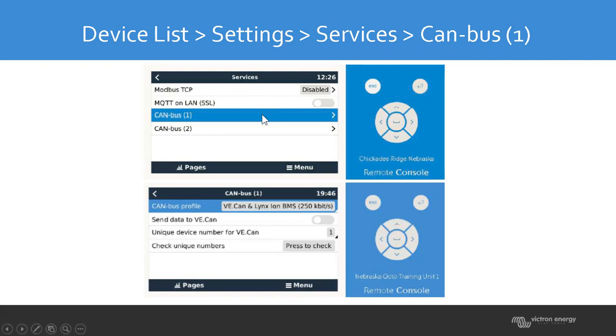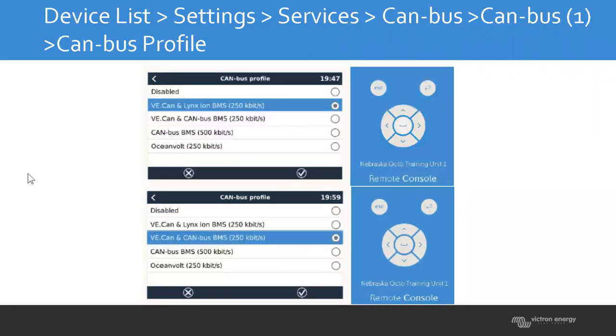This is a shot you'll see of the CAN bus. We get into that CAN bus, and it'll say CAN bus 1. Once you get into that, the CAN bus profile is going to show VE CAN and Lynx Ion, that's the default, and we're going to have to change that. So we get into that menu, and it'll come up with the top screenshot here, VE CAN and Lynx Ion BMS. We want to change that to VE CAN and CAN bus BMS at the 250 kilobit range.